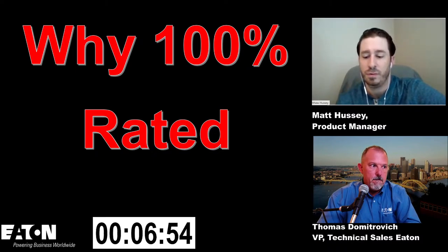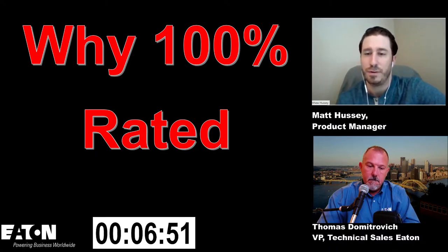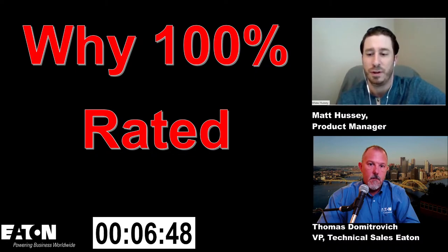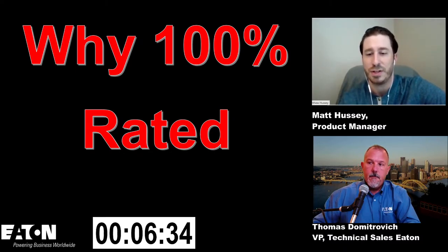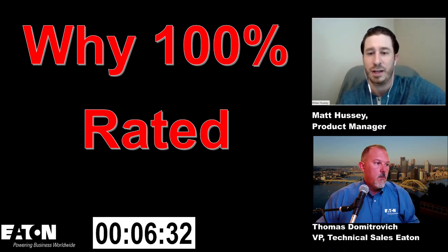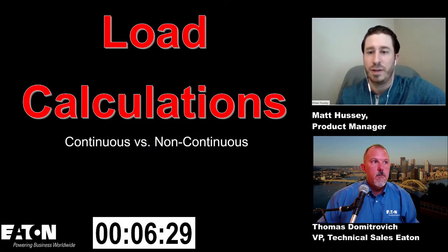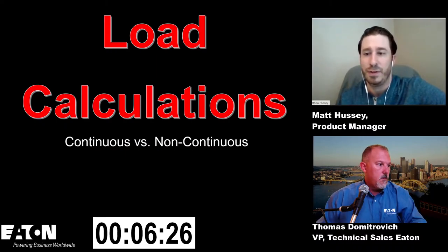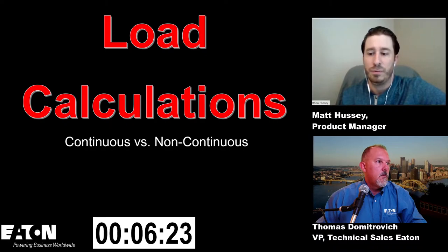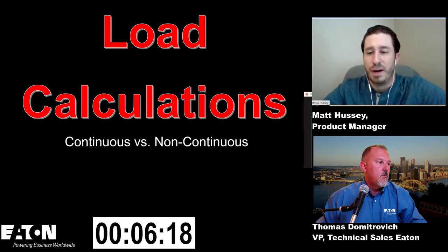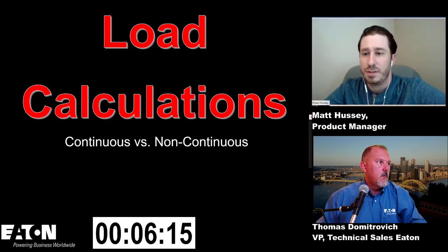If you go back into how those overcurrent protective devices are tested, it actually aligns with it: when they get a certain ampacity rating, it backs up and supports how they're done. So what you really have going on is a heat mass equation, where that disconnect is expecting a certain amount of cabling to be present downstream of it. If you decrease the amount there, it's allowing for more heat to build up around that overcurrent protective device.